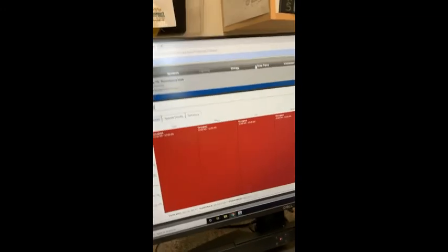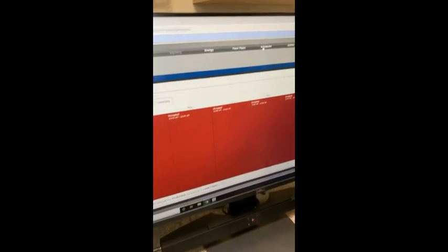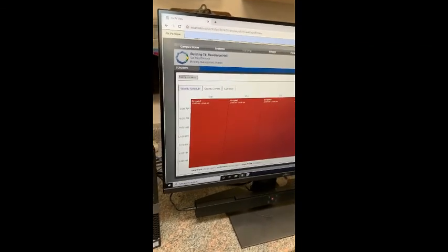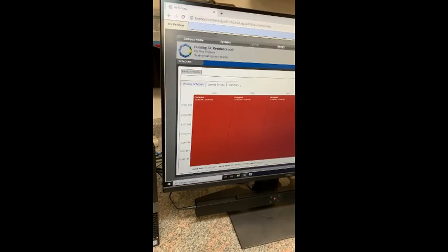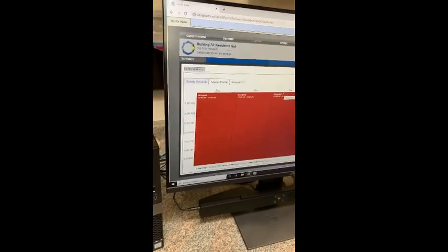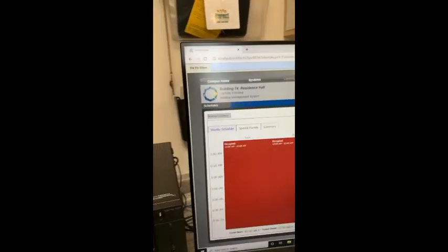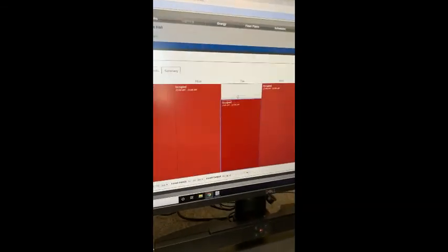There is the next, there's a schedules page. So this is for all the common areas, the VAVs and their air handlers. Right now the schedules are just set for 24/7. The way that you can change those, and again, admin or power user can only do this, a user cannot, you just click and drag.